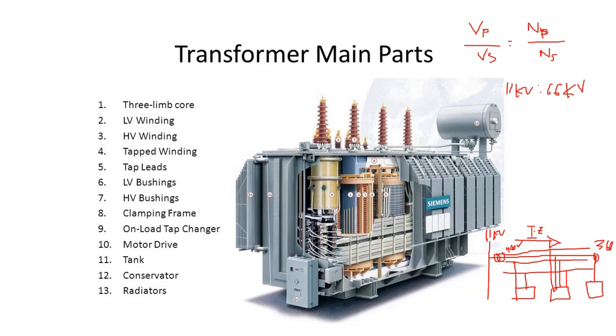One way to overcome this issue with the voltage is to have a variable turns ratio. So instead of having a fixed 11 kilovolt to 400 volt transformer, if you have a turns ratio in the secondary which can be increased when the load is high, then instead of 400 volt you can maybe have 420 volt. In that case, with a fixed turns ratio you may not have control of the voltage at the end of the line, but with the help of this variable turns ratio it is possible to have control over the voltage.